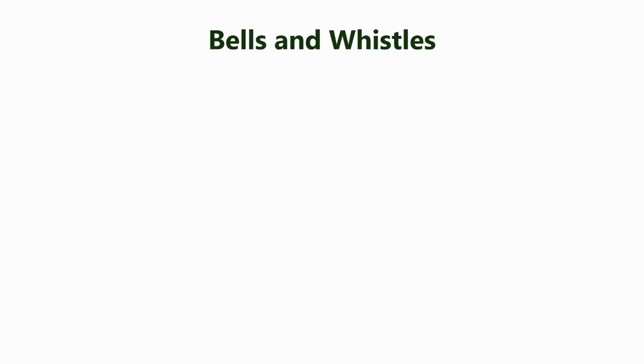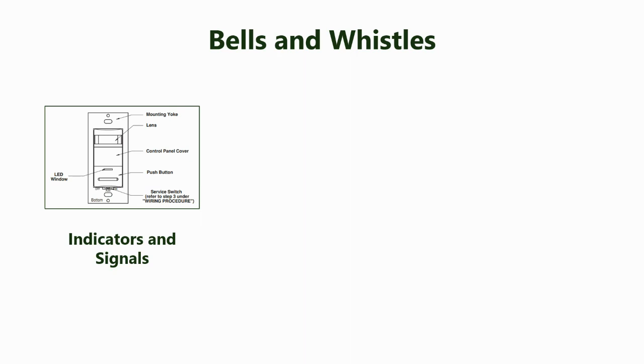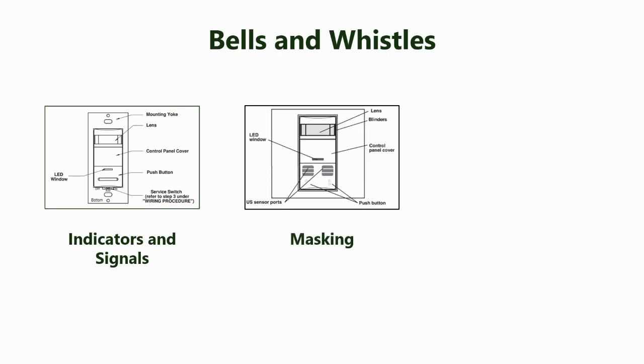All sensors have some sort of special feature particular to their brand or style. Common features include indicators and signals — most sensors indicate motion is detected using an LED indicator light, and some sensors even emit a sound shortly before turning off. Passive infrared sensors require a line of sight to activate, so their field of view may be adjusted using masking labels, blinders, or shutters. This allows, for example, a sensor to cover a private office but not an adjacent hallway, preventing activation when someone walks past with the door open.